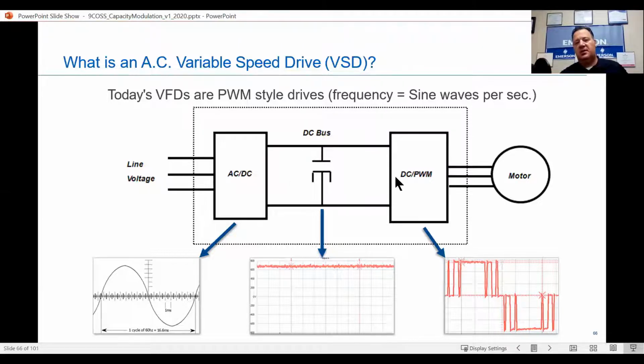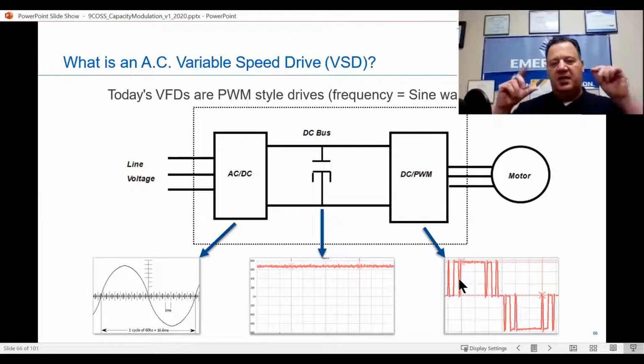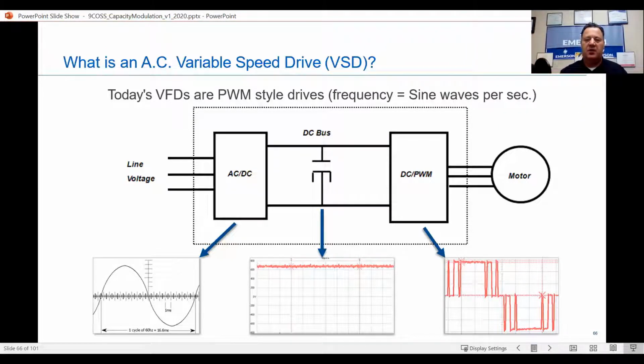And then our DC, we're going to go back to pulse width modulation. Now, this pulse width modulation might look a little confusing, but really, all it's telling you is how long those switches, or insulated gate bipolar transistors, IGBTs, are open and closed. So by opening and closing those, we're changing that current, and the DC looks like AC. We're really manipulating the hertz of the motor, okay? We're manipulating the frequency, and we're slowing that motor down or raising it up at a gradual speed. And that's how variable speed works.